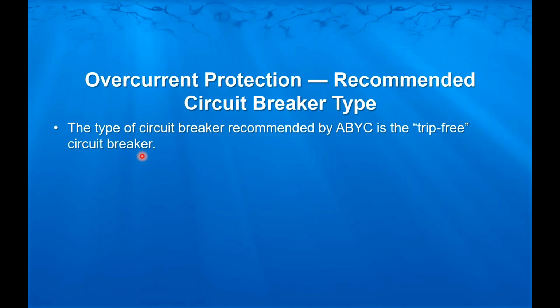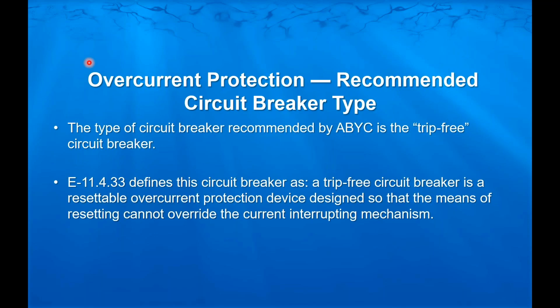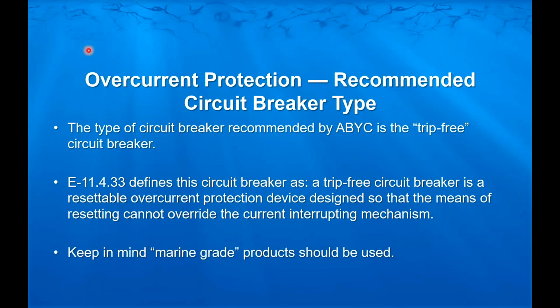The type of circuit breakers recommended by ABYC is what's called a trip-free circuit breaker. Trip-free circuit breaker is defined in the standards as a resettable overcurrent protection device designed so that the means of resetting cannot override the current interrupting mechanism. This means that you cannot hold the breaker in position if a fault still occurs. Any of you with experience with these breakers will know they will not reset to any extent when you try to push the breaker back over to reset it if the fault still exists. And again, in all cases, everything we use, you should always use marine grade products.